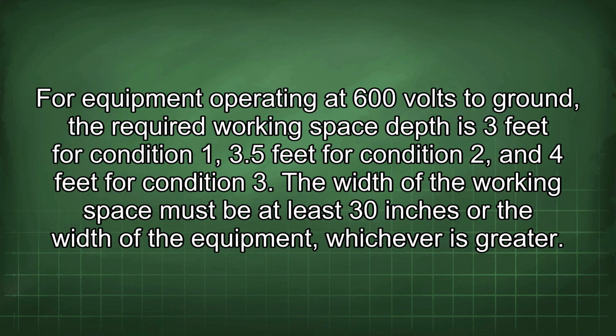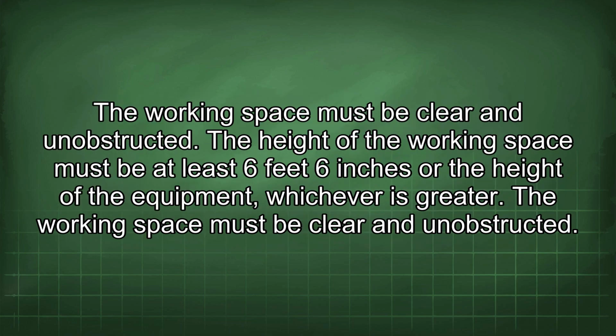The width of the working space must be at least 30 inches or the width of the equipment, whichever is greater. The working space must be clear and unobstructed. The height of the working space must be at least 6 feet 6 inches or the height of the equipment, whichever is greater. The working space must be clear and unobstructed.